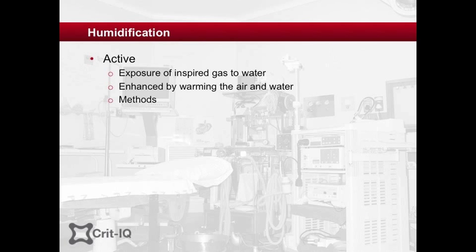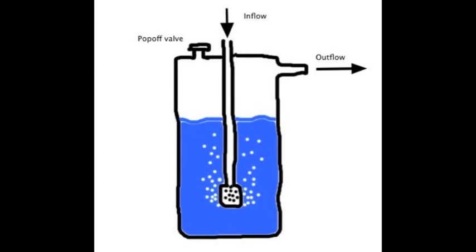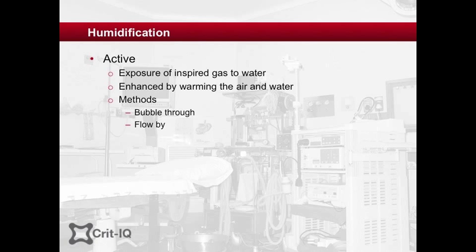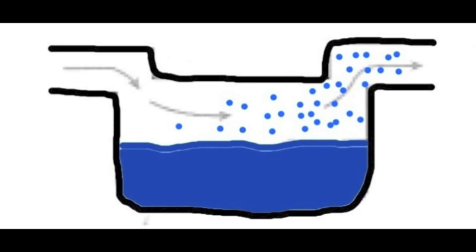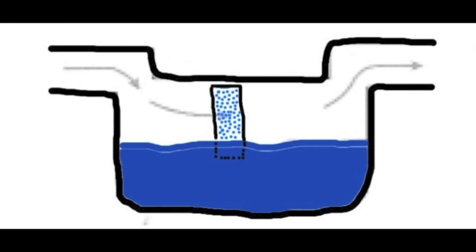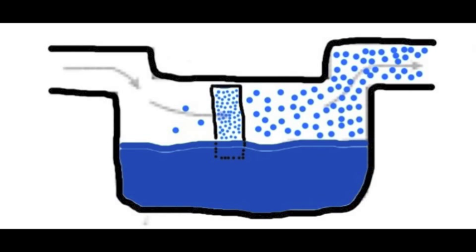Two basic forms include the bubble-through and the flow-by mechanisms. In the former, the air flow is actively bubbled through a diffuser in a chamber of warmed sterile water. They are limited by the flow that can be facilitated, so are generally not suitable for mechanical ventilators. In the latter mechanism, the air flow passes over a bath of heated sterile water, picking up moisture and warmth as it goes. The addition of a thin, permeable, absorbent material known as a wick significantly increases the efficiency of this type of humidifier.